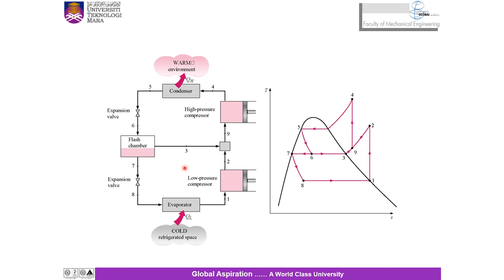In this system, liquid refrigerant expands in the first expansion valve to the flash chamber pressure, which is the same as the compressor interstage pressure. Part of the liquid vaporizes during this process. This saturated vapor, state 3, is mixed with the superheated vapor from the low pressure compressor, state 2 — you can see the mixing here from point 3 to point 2. The mixture then enters the high pressure compressor at state 9.